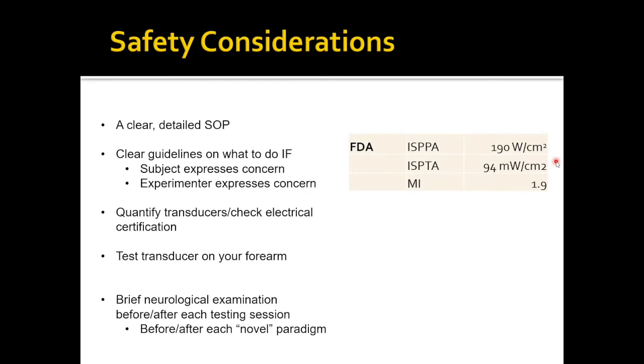Of course, quantify your transducers and check your electrical certifications. Some universities require that your transducer and anything plugged into the wall, mostly your amplifier, has the relevant electrical certification so the insulation doesn't melt or start a fire. Fairly basic things. Quantifying your transducers in free water with a hydrophone setup is extremely important to establish baseline readings of the intensities expected at various foci and axial distances.